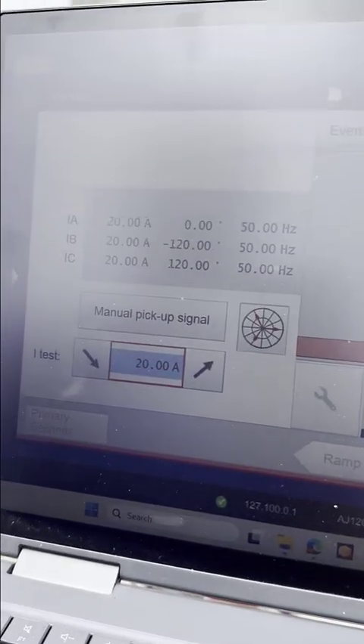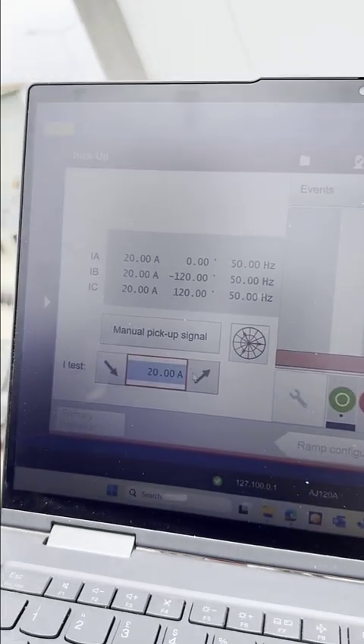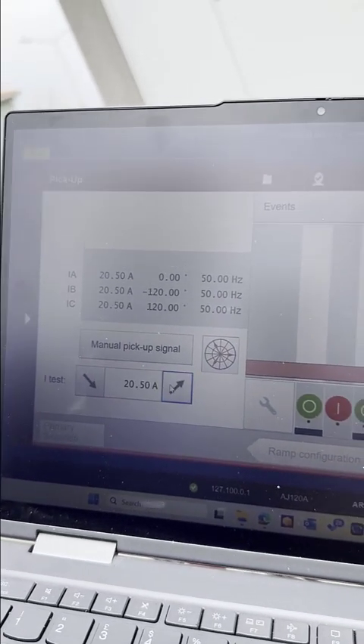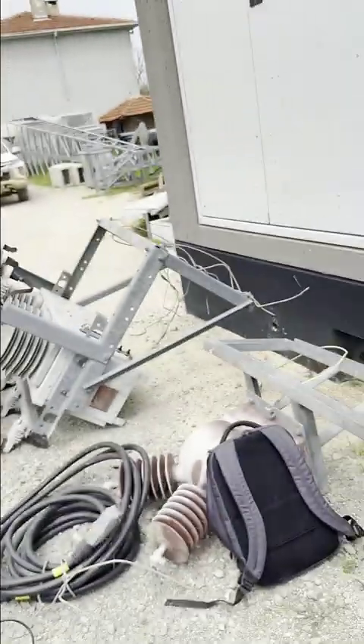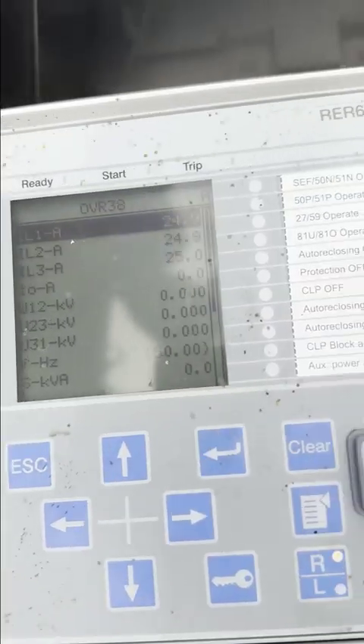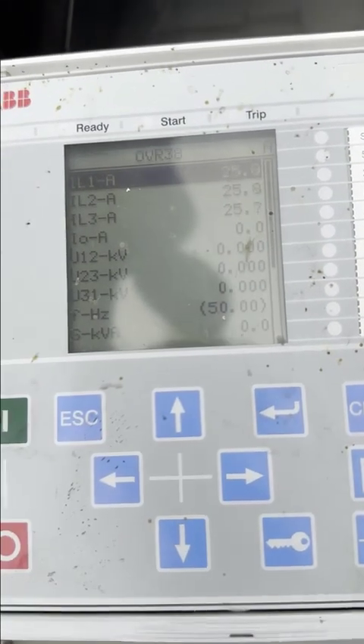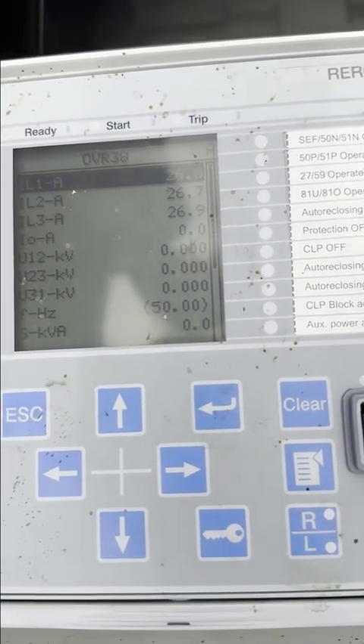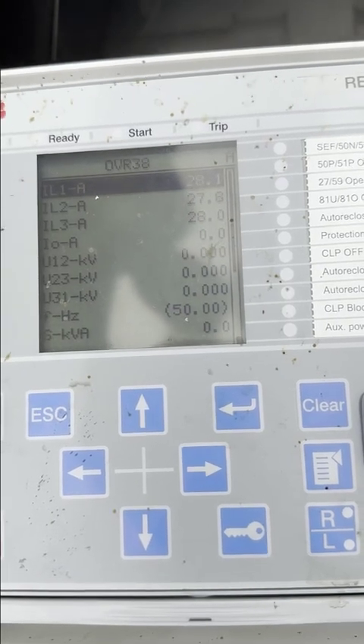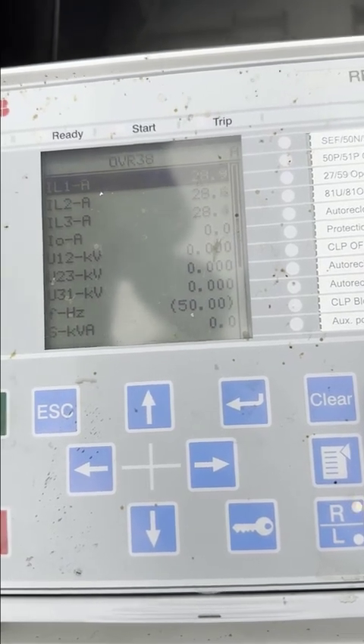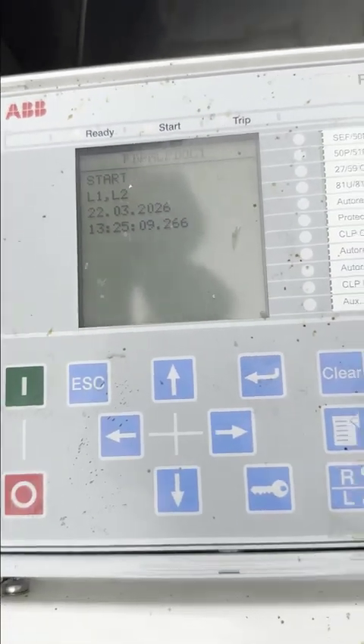As you can see now, I will start the IO button to start injection, and here is the injection window, which is highlighted by red, as you can see. And here's the value right now. So I will increase it until it reaches 30 amp, which is the backup of the first stage. You can see now from the relay, now it's 25, 26, 26.5. You can see the measurement. Now it's 29, 29.5, and now it's 30. You can see now the backup as the start contact of the L1 and L2.